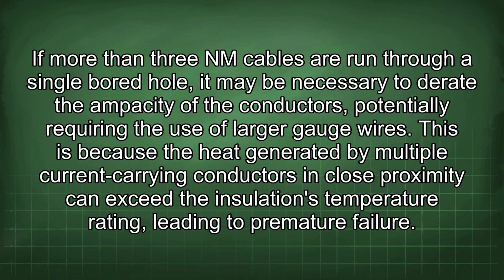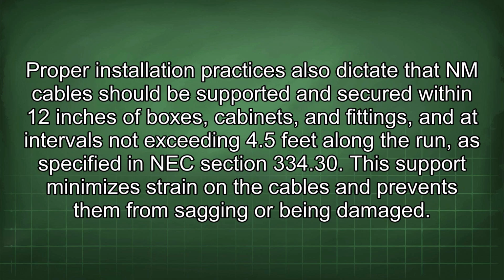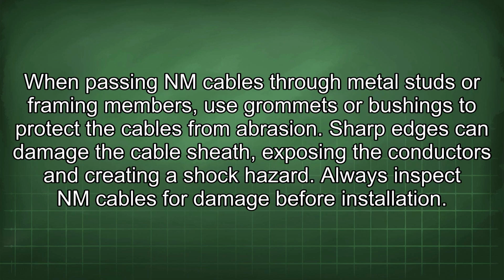to premature failure. Proper installation practices also dictate that NM cables should be supported and secured within 12 inches of boxes, cabinets, and fittings, and at intervals not exceeding 4.5 feet along the run, as specified in NEC Section 334.30. This support minimizes strain on the cables and prevents them from sagging or being damaged. When passing NM cables through metal studs or framing members, use grommets or bushings to protect the cables from abrasion. Sharp edges can damage the cable sheath, exposing the conductors and creating a shock hazard.